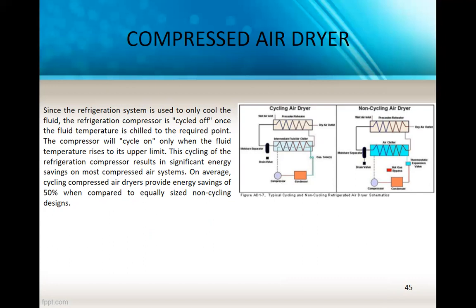The cycling of the refrigeration compressor results in significant energy savings on most compressed air systems. An average cycling compressed air dryer provides energy savings of 50% when compared to an equally sized non-cycling design. Okay? Dalawang type ng refrigerated air dryer.